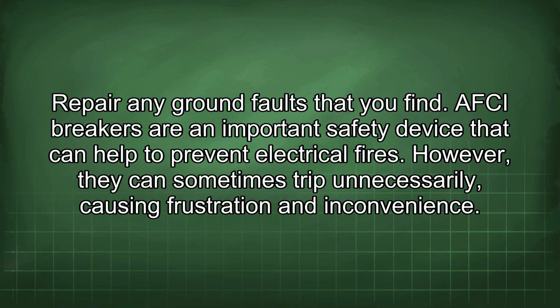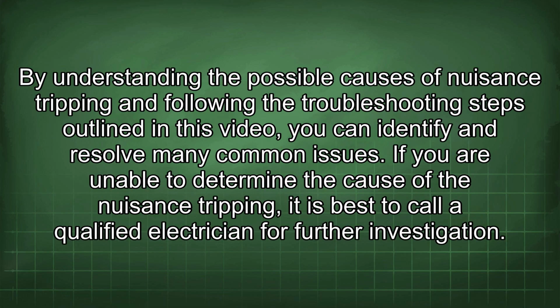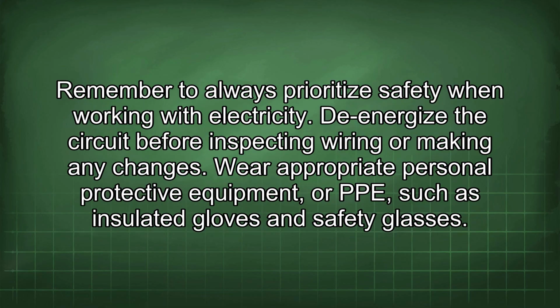AFCI breakers are an important safety device that can help to prevent electrical fires. However, they can sometimes trip unnecessarily, causing frustration and inconvenience. By understanding the possible causes of nuisance tripping and following the troubleshooting steps outlined in this video, you can identify and resolve many common issues. If you are unable to determine the cause of the nuisance tripping, it is best to call a qualified electrician for further investigation. Remember to always prioritize safety when working with electricity.